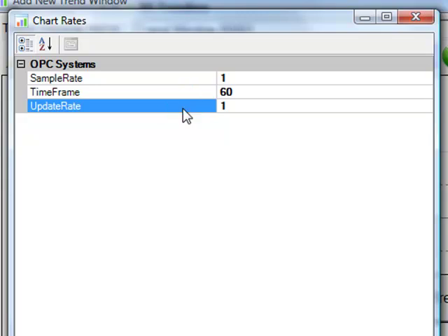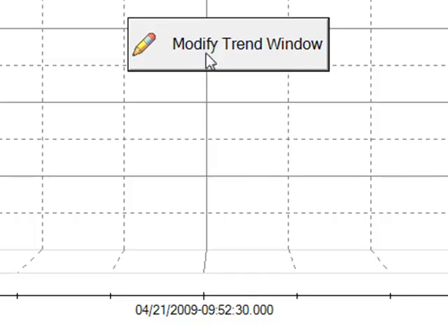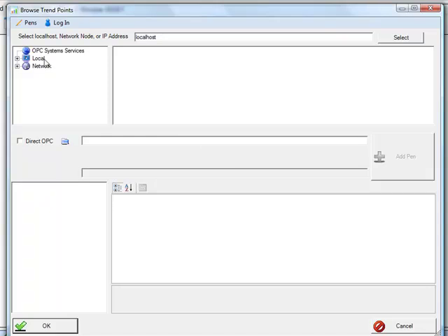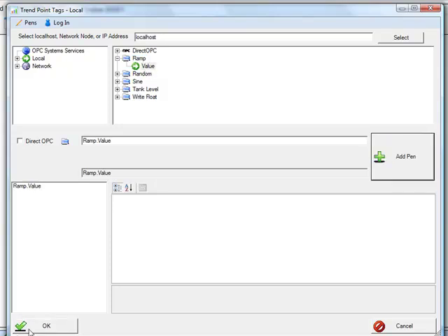The overall time frame can be anything that you would like, and this is the real-time time frame. Another property we might want to modify is the pens property. Here we can select what pens we want to obtain data from. We can select the local service to bring up tags defined for trending in the local system, or we can enter an IP address, network node name, or registered domain name and actually browse and connect and trend real-time data from a remote system, even across the internet. Here I'm going to select the signal ramp value.